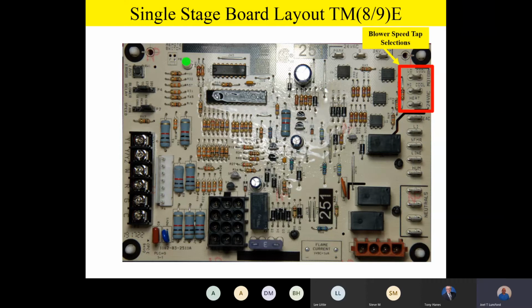And as a quick reminder, team, we always design our ductwork and we always set up our speed taps on cooling for 400 CFM per ton of cooling. And then on the heating speed, we want to make sure and look at the data plate on the furnace. If you'll take the service panels off the front of the furnace and turn them around, you're going to notice there's a data plate in there.